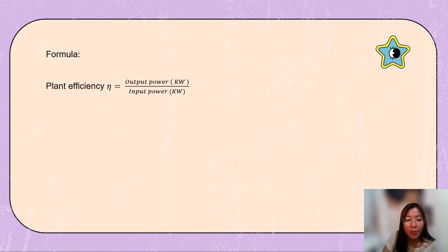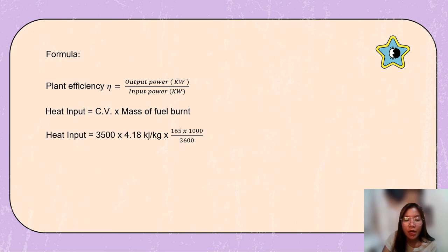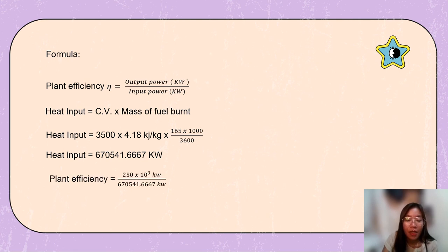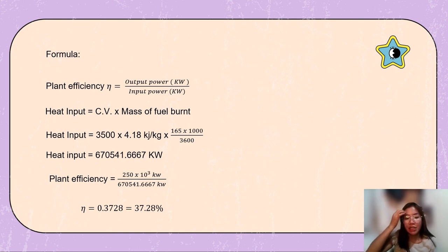To find the overall efficiency, the formula is: plant efficiency equals output power over input power. Heat input equals calorific value times mass of fuel burned: 3,500 × 4.18 kJ/kg × (165 × 1000 ÷ 3600). The heat input equals 670,541.667 kilowatts. Therefore, plant efficiency equals 250 × 10³ ÷ 670,541.667, giving a plant efficiency of 0.3728, or 37.28%.